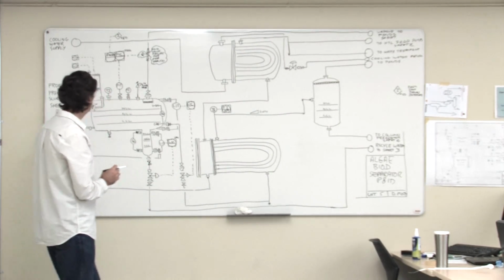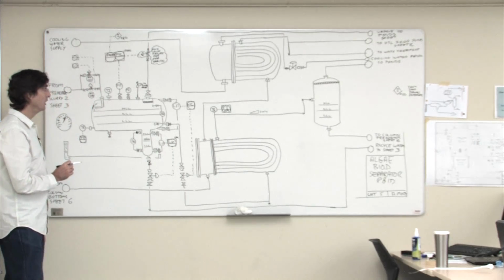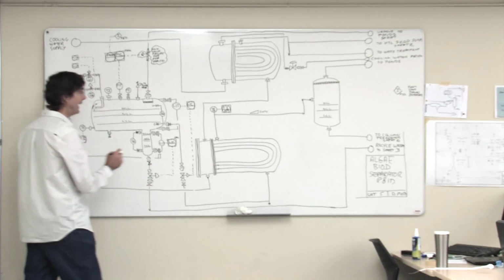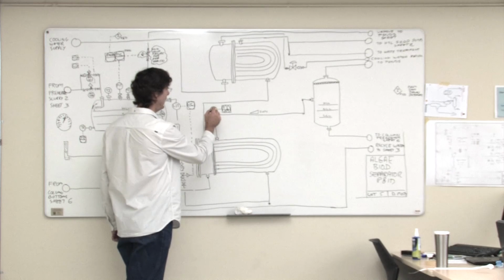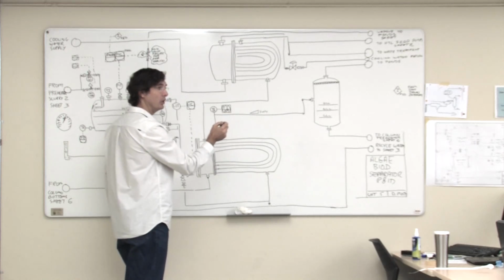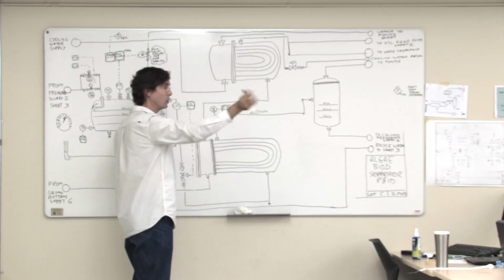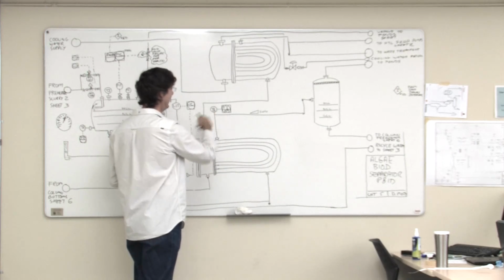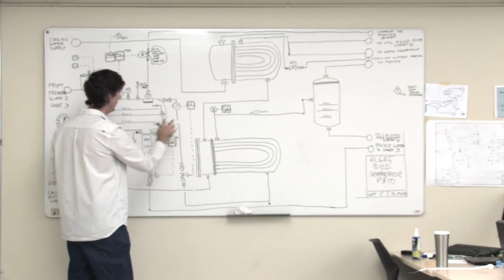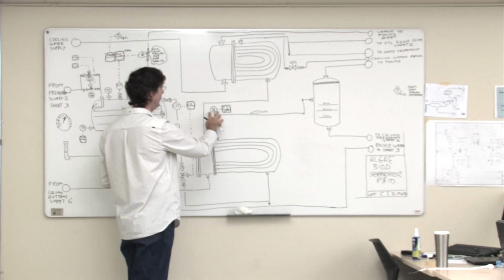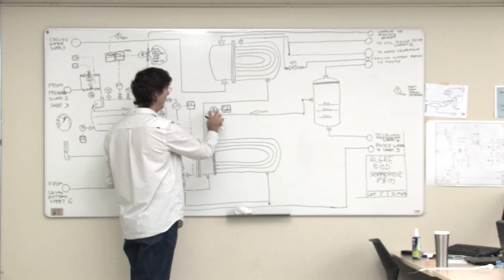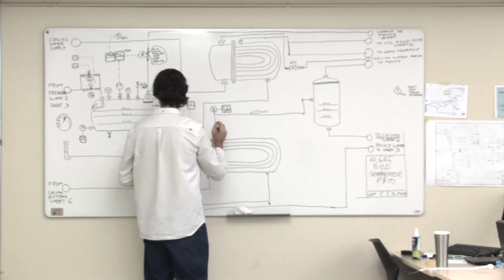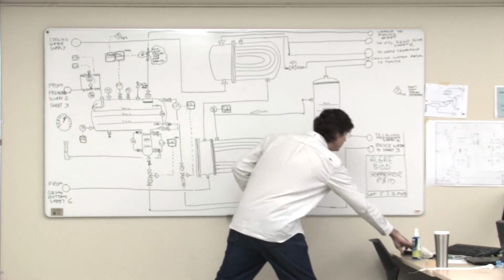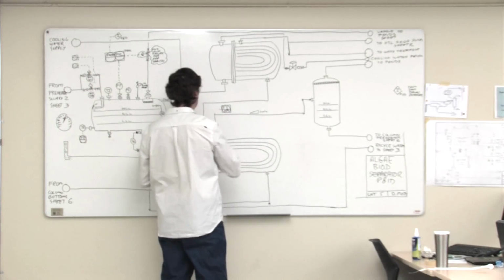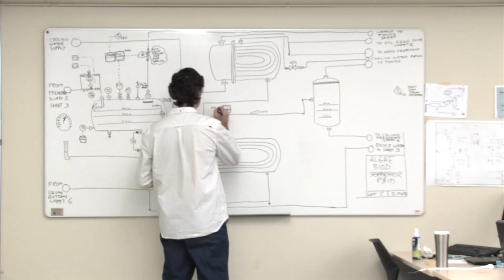A TI can generally not. What you can do is provide a temperature indicating transmitter. Most of the TEs are just wired straight back to the DCS, and you don't need a transmitter, unlike level and pressure. If you really want to be able to read the temperature out in the field, then you put a TIT in. So if you wanted to do that, let's say we did, just for argument's sake.